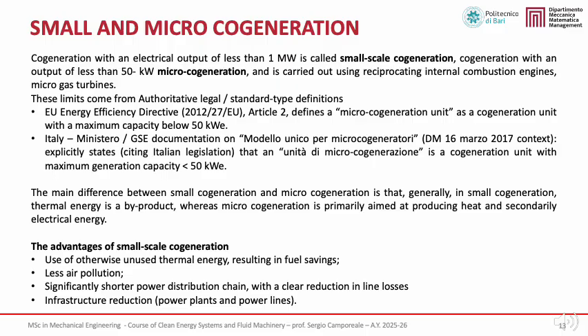From a technological point of view, small and micro cogeneration systems are typically based on reciprocating internal combustion engines or microgas turbines, which are well suited for decentralized and distributed installations. A key distinction between small scale and micro cogeneration concerns the primary energy objective. In small scale cogeneration, electricity production is usually the main goal, while thermal energy is recovered as a byproduct. In contrast, micro cogeneration systems are primarily designed to produce heat, with electricity generated as a secondary output to support local consumption. Small scale cogeneration offers several important advantages.